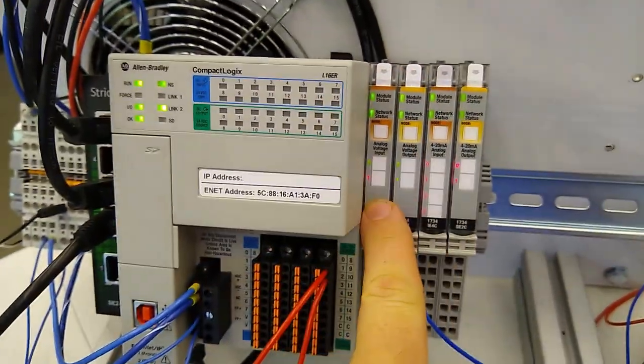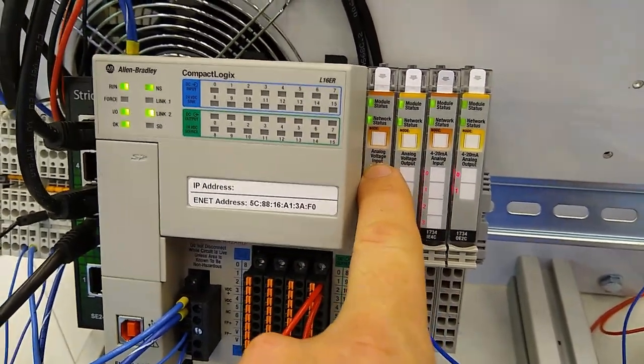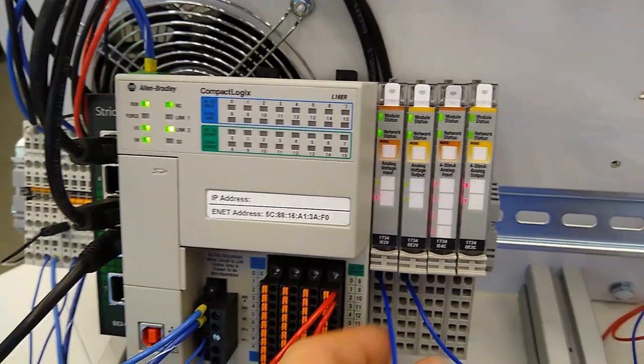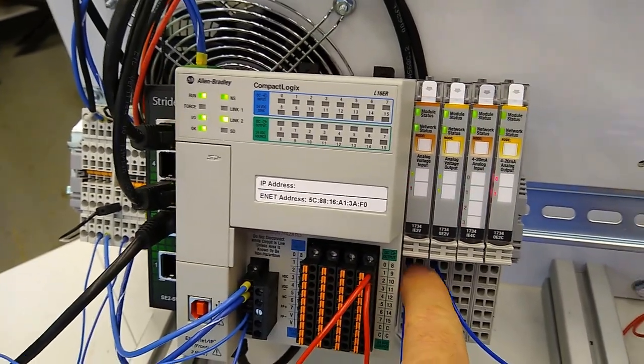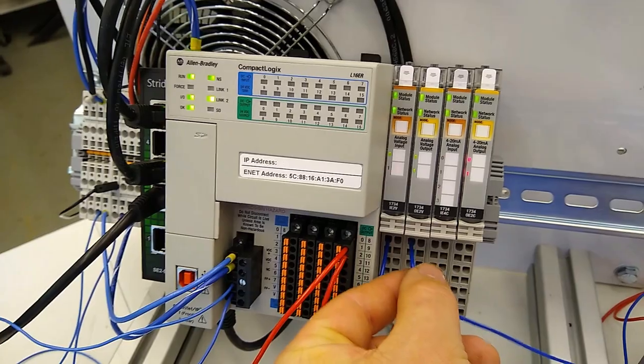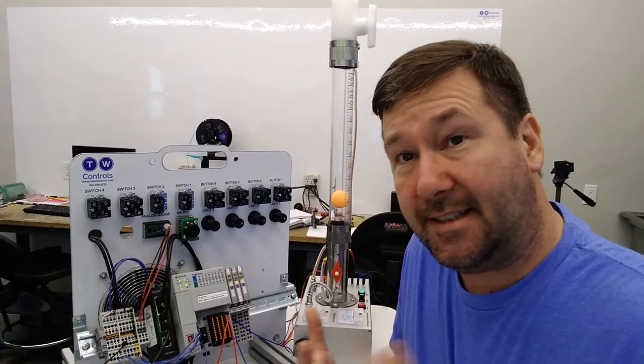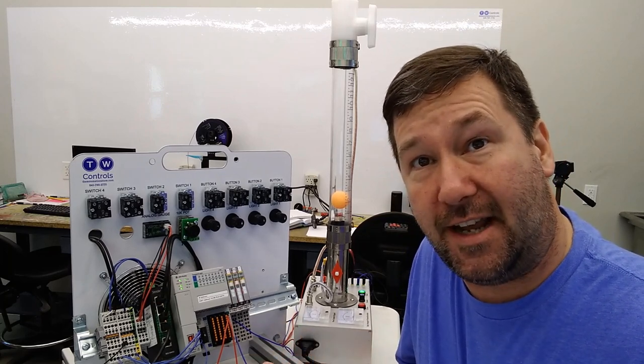And those are going to go over to our analog modules here and this one is a voltage input module and this is a voltage output. That's the two we are going to use. And our analog prox plus is going to analog input zero and our fan speed command is coming from analog output zero. And that's all it's going to take to interface these two trainers. That's why this was such a natural fit.